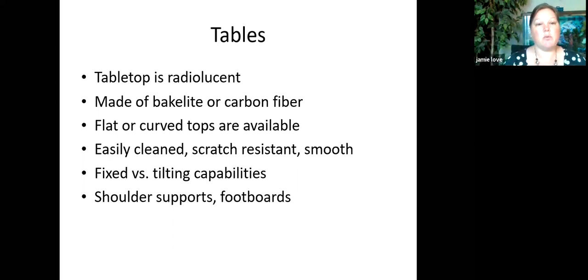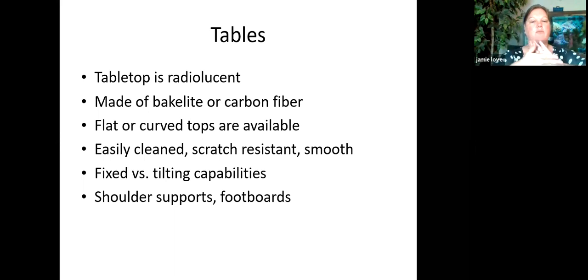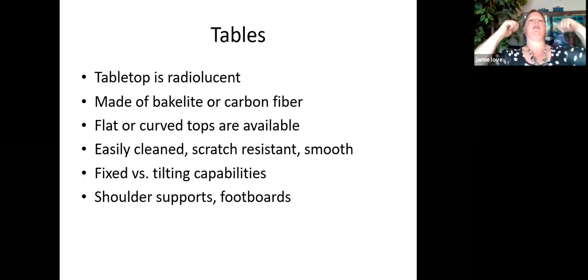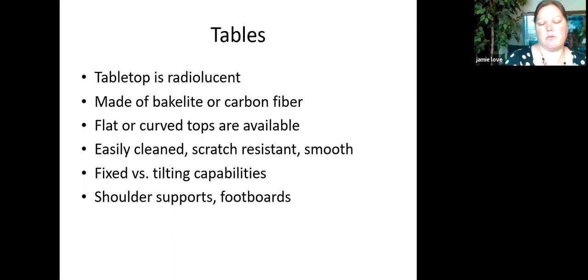A fluoro table, we want to be able to tilt and stand it up and then lay it flat. So it's two different types of movements for our tables, fixed or tilting tables. And then if we're tilting, we're going to need some kind of support at the bottom for our feet for the patient not to slide off the table, or shoulder supports at the top. So if we do head down, they don't slide off the back of the table the other way.